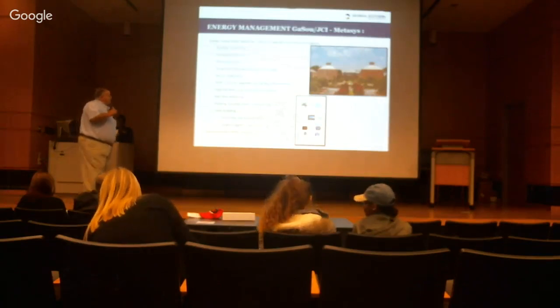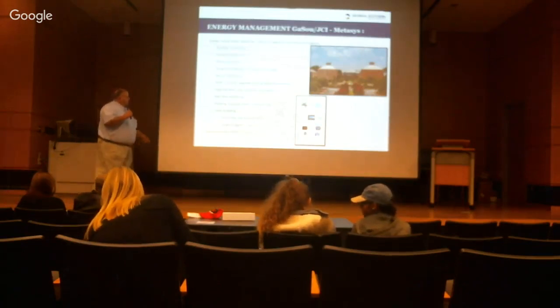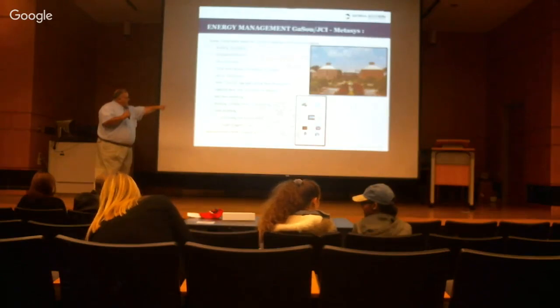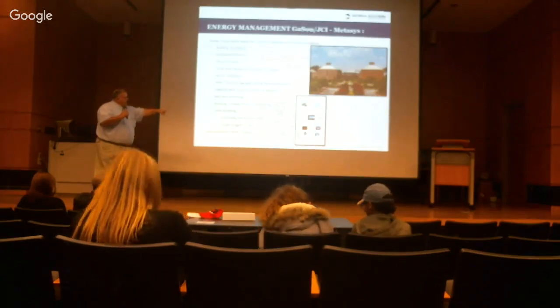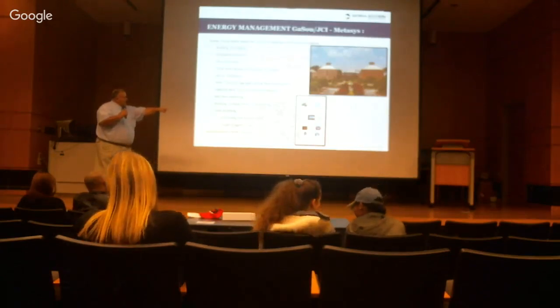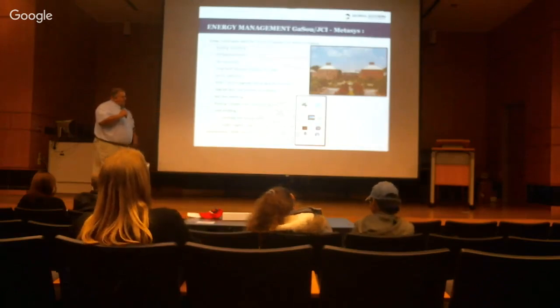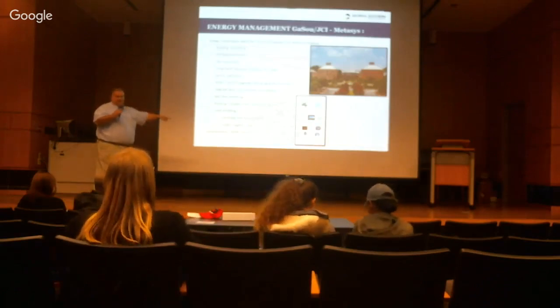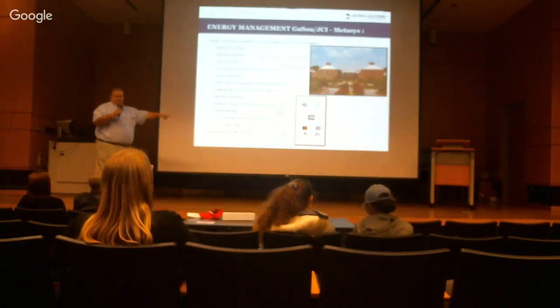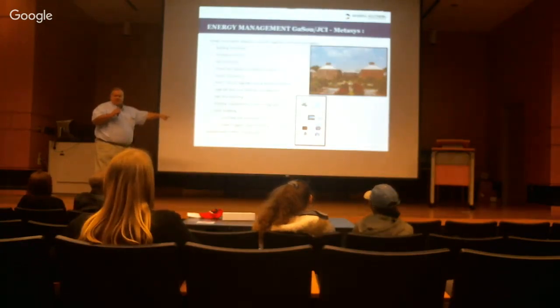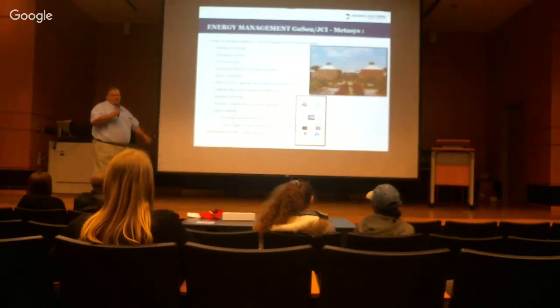One key feature is down here at the bottom — we load shed during extremely hot times. We have a targeted triggering load shedding system for the summer, and it offsets real money every year. Those are actual savings dollars, not just projected, measured against the bill from the power company. They told us how much we saved.